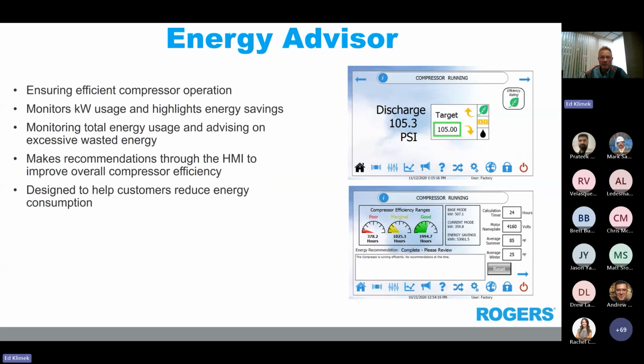Like every system is different, they may not use a leaf, it may just be through text. But in this situation, if the rating is marginal it would be yellow, and poor would be red. The Energy Advisor will periodically make recommendations on methods that can improve the overall operation. These recommendations can include suggestions to change control modes or maybe enable your auto unload or start/stop features. So the Energy Advisor basically will tell you where your system is performing poorly and recommend what type of control mode you should operate in. It will also tell you your kilowatt usage based on the control mode that you're operating in.